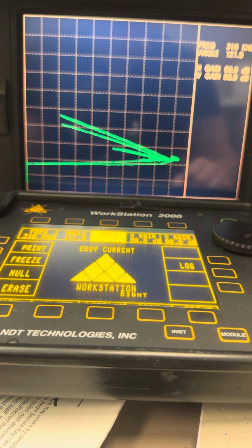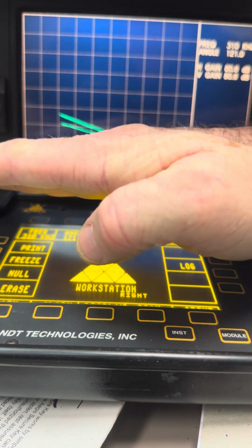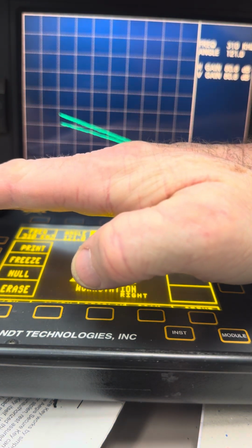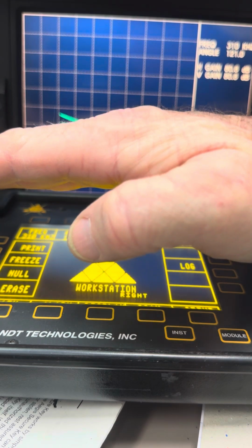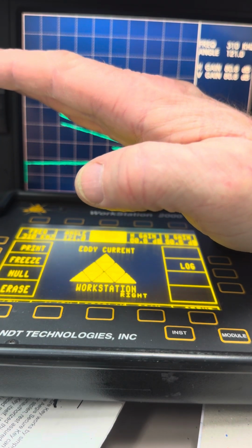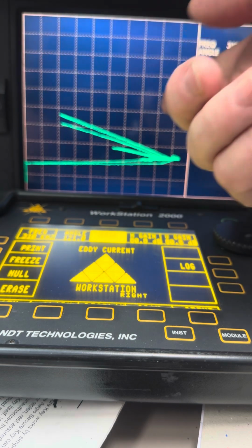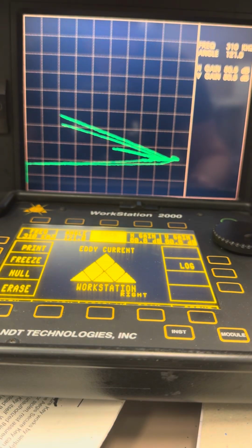And when you're talking about F90 test frequencies or F120, that's the frequency that gives you the required phase separation between your ID and OD flaws. And you're going to need to know what it means. All it means is, if you take liftoff that's horizontal, right now the separation angle between that and this deep EDM notch, which is like, what, 35 degrees? That's a separation angle of 35 degrees, not rocket science.